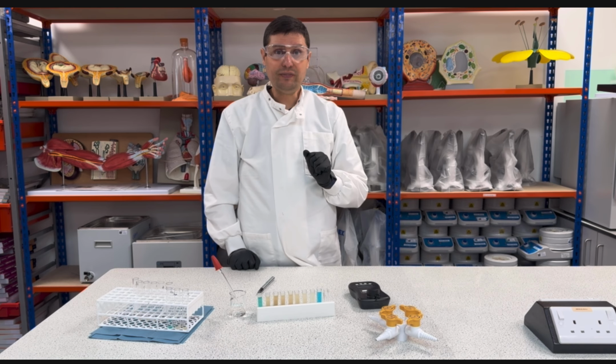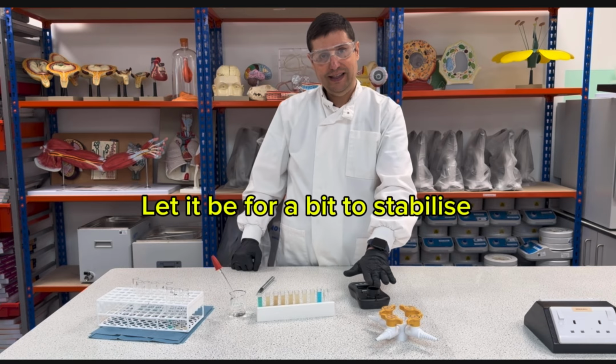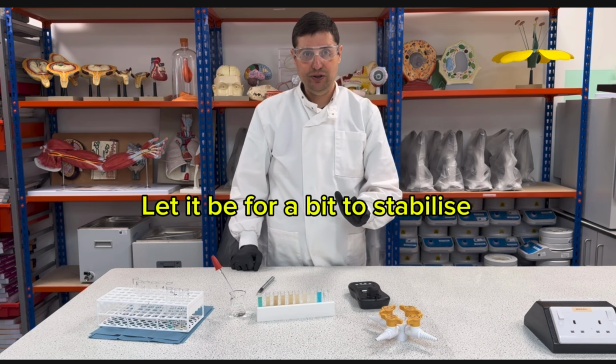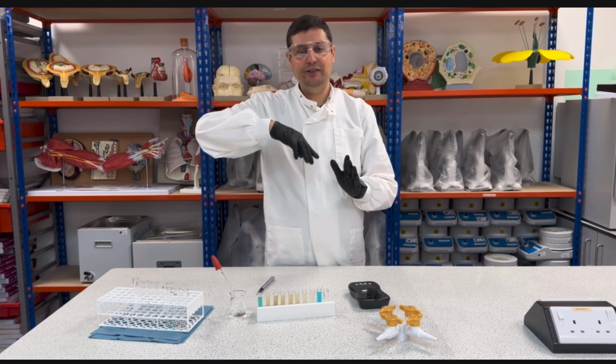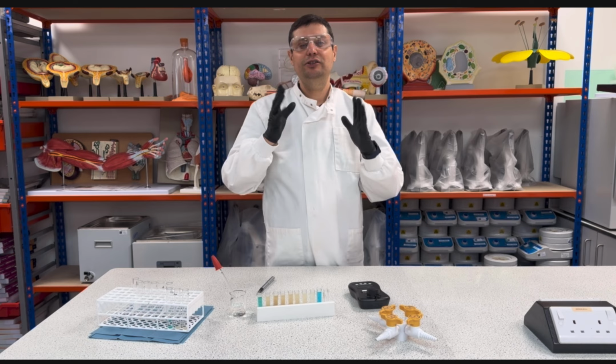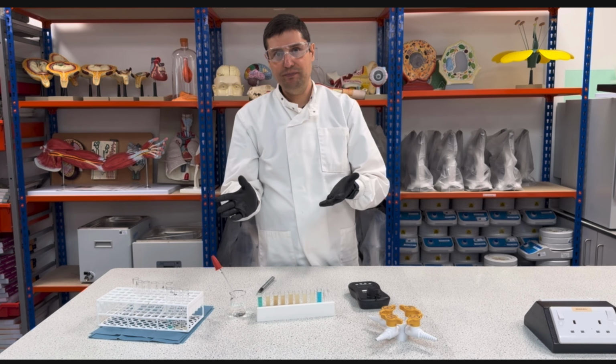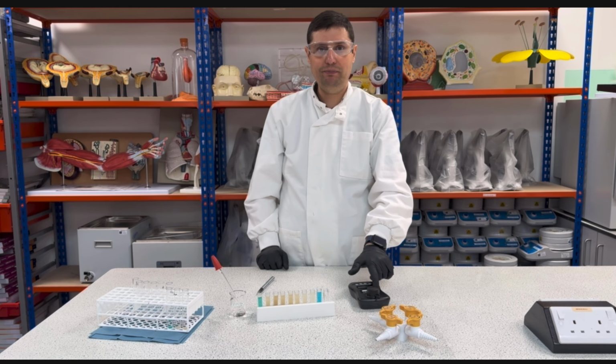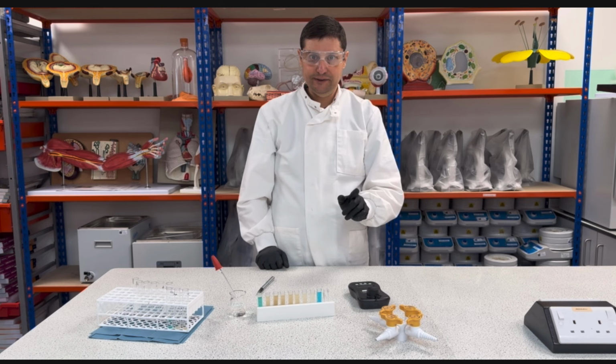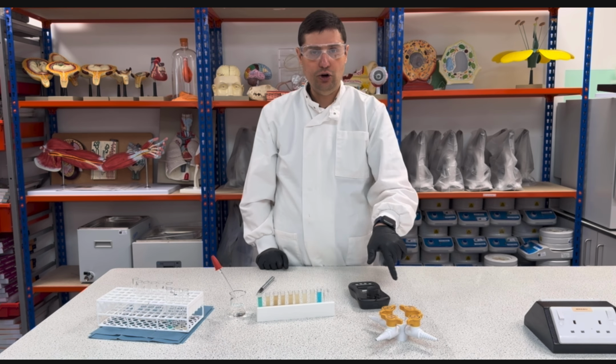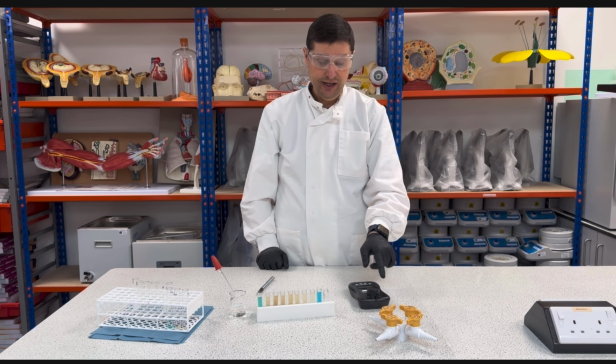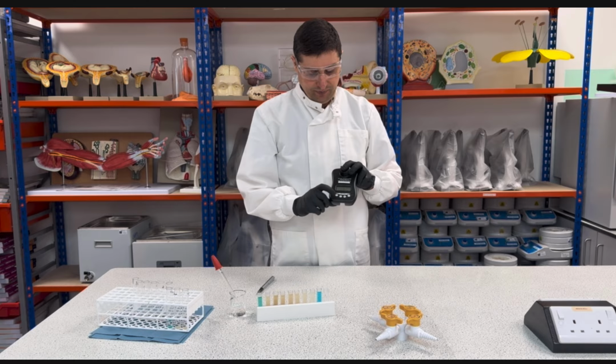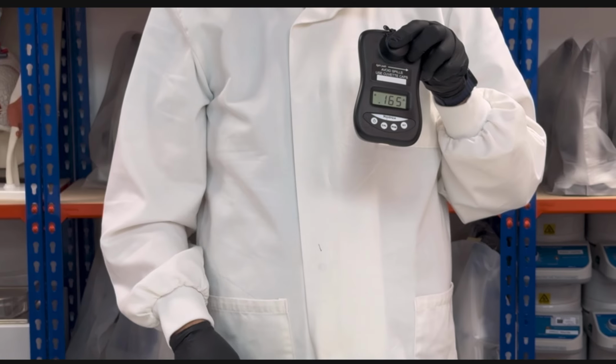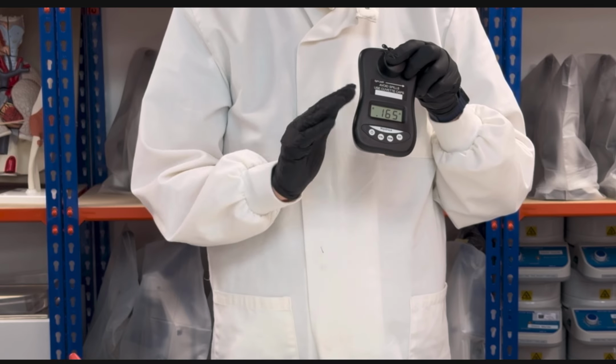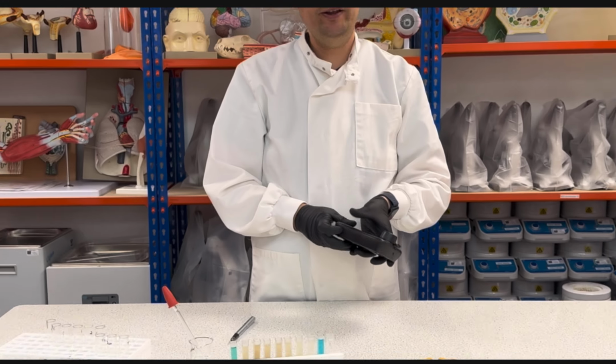Another thing, after you place it inside the machine, let it be for a bit to stabilize, okay? If you see the numbers going up and down, this means the solution is not stable yet. So let it be for a couple of seconds and then you take the reading. And what might happen as well, for saving power, the machine will turn off. But even if the machine turns off, all the calibration will still save in the memory. So you just need to press the on again, and this will come back for your final calibration results. Okay, so this is going to be saved here. So even if this goes off, just press on again, and then you carry on with your readings.